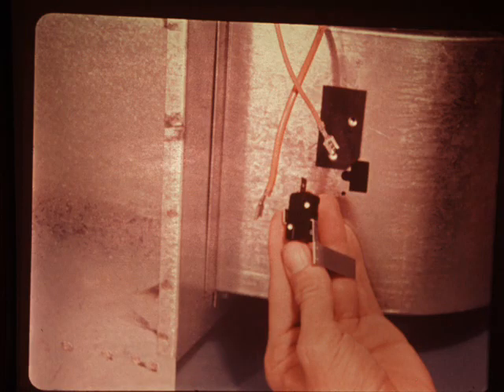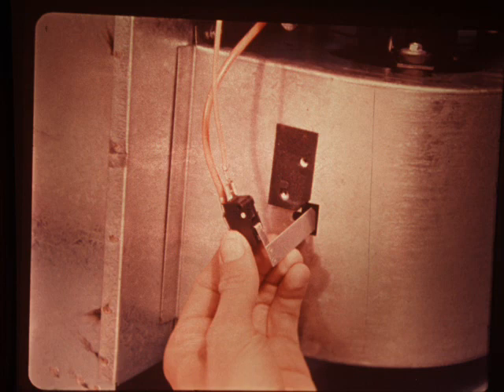Removal of the sail switch is also just a matter of disconnecting the electrical leads and removing 2 mounting screws. Take care not to damage it when pulling it out of the bottom of the blower housing. Take care, too, when reinstalling this switch. Be sure the sail arm does not contact the sheet metal of the blower housing.